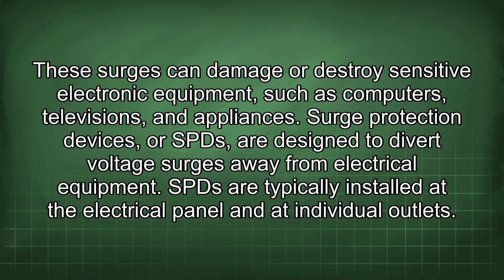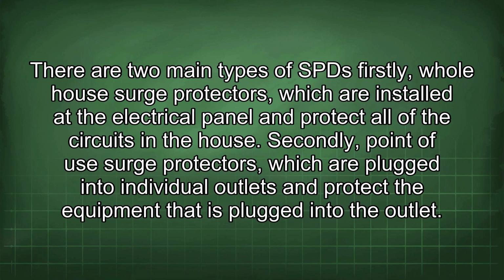Surge protection devices, or SPDs, are designed to divert voltage surges away from electrical equipment. SPDs are typically installed at the electrical panel and at individual outlets. There are two main types of SPD. Firstly, whole-house surge protectors, which are installed at the electrical panel and protect all of the circuits in the house. Secondly, point-of-use surge protectors, which are plugged into individual outlets and protect the equipment that is plugged into the outlet.